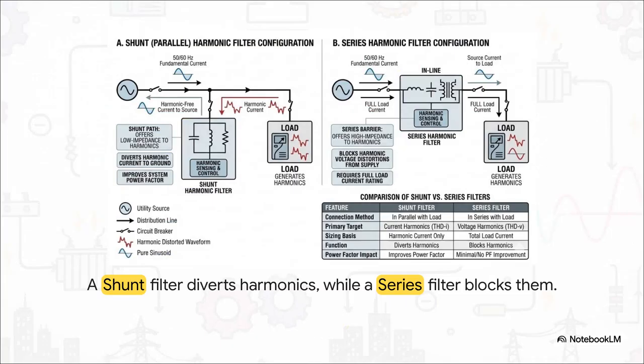This diagram perfectly shows the two main ways they get installed. On the left, you see a shunt filter. It connects in parallel to the main circuit—that's our off-ramp we were talking about. It's actively pulling those nasty harmonic currents out of the main flow. On the right, you have a series filter. This one's placed directly in line with the circuit, and it acts more like a gatekeeper or a barrier that literally blocks the harmonics from getting through.